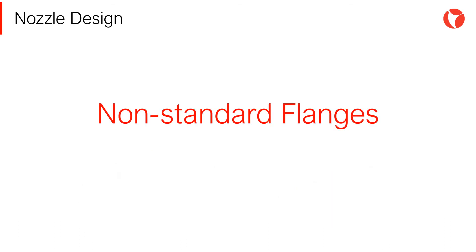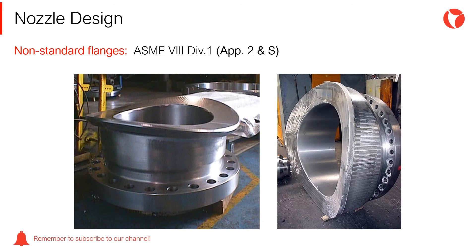When pressure, temperature, and size requirements exceed the capabilities of standard flanges, non-standard ones shall be used. We should keep in mind that non-standard flanges require calculation, design, and special manufacturing processes. These elements are very costly and require long lead time, which is why they are chosen only as a last resort.